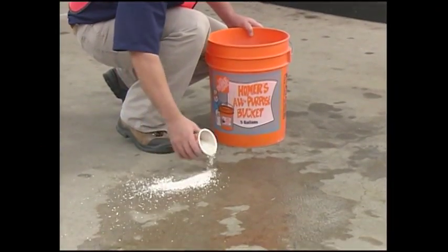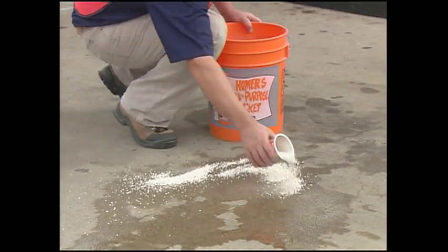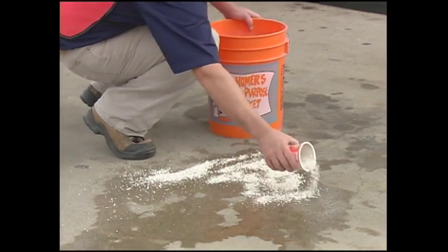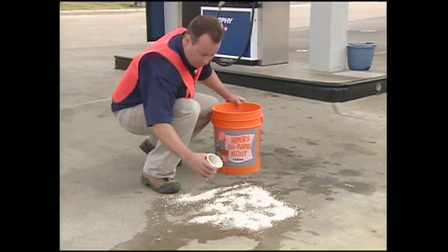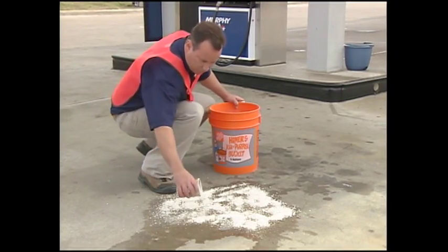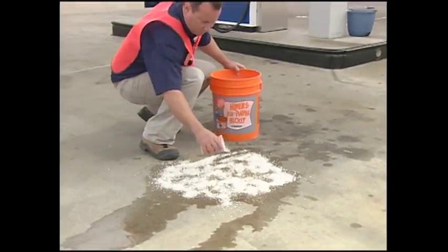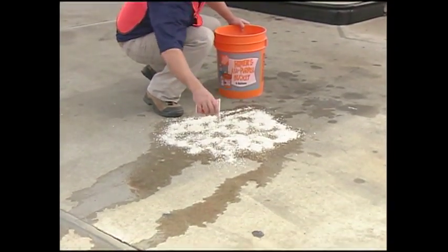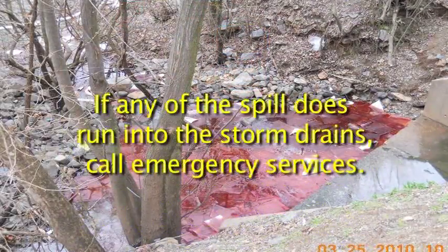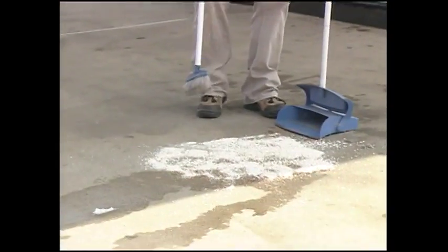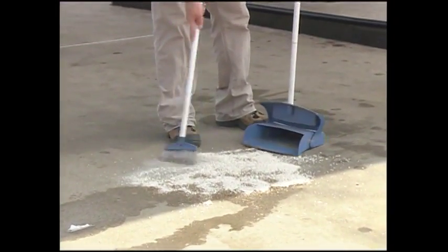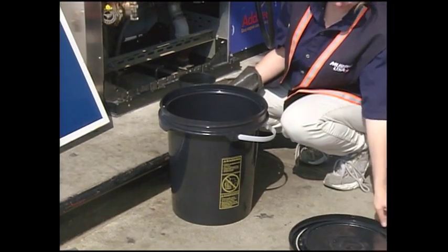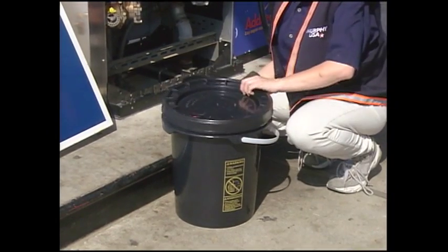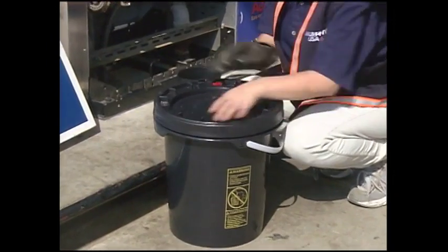If it's safe to do so, there is no apparent danger of ignition, you should contain, absorb, and clean up any surface spills. Spread absorbent such as floor dry or kitty litter around the edge of the spill to keep it from spreading or running into storm drains. If any of the spill does run into storm drains, call emergency services. Once the absorbent material has soaked up the spill, sweep it up. Put it in a labeled and sealed container and place it behind the building for pickup. Do not put it in a dumpster.